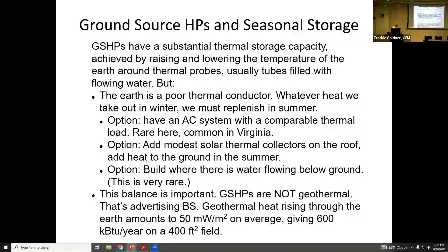But you can make a system that works pretty well. And these people made a largely solar heat pump system in Okotoks, Alberta, where the design point temperature is minus 27 F. And they have got a collection of heat pumps in their houses, and the supply water for the heat pumps is shared between them and between other buildings as well. And it's pumped up and down into the ground.